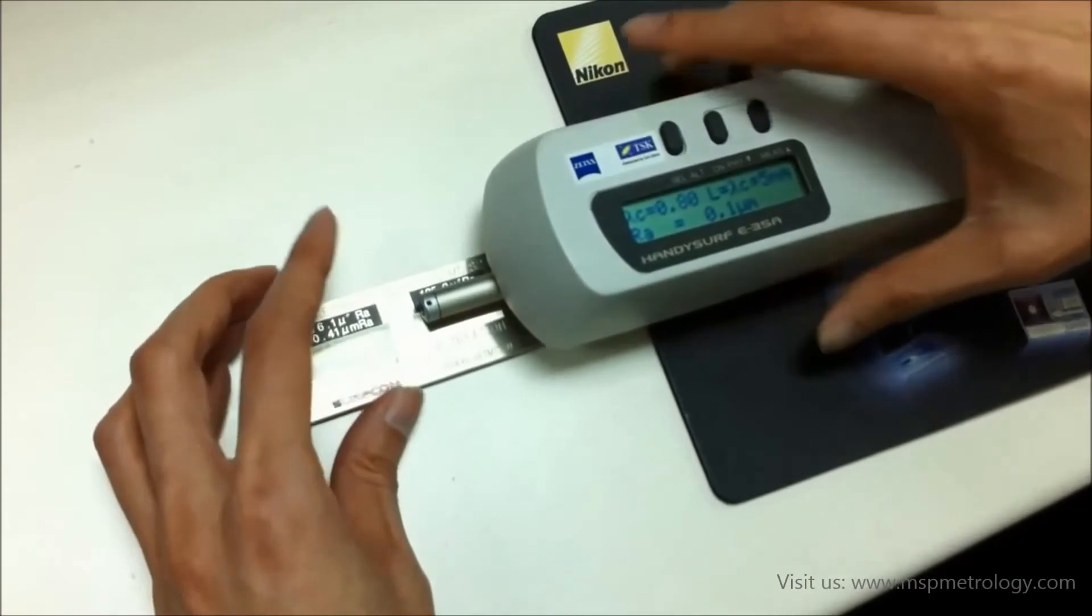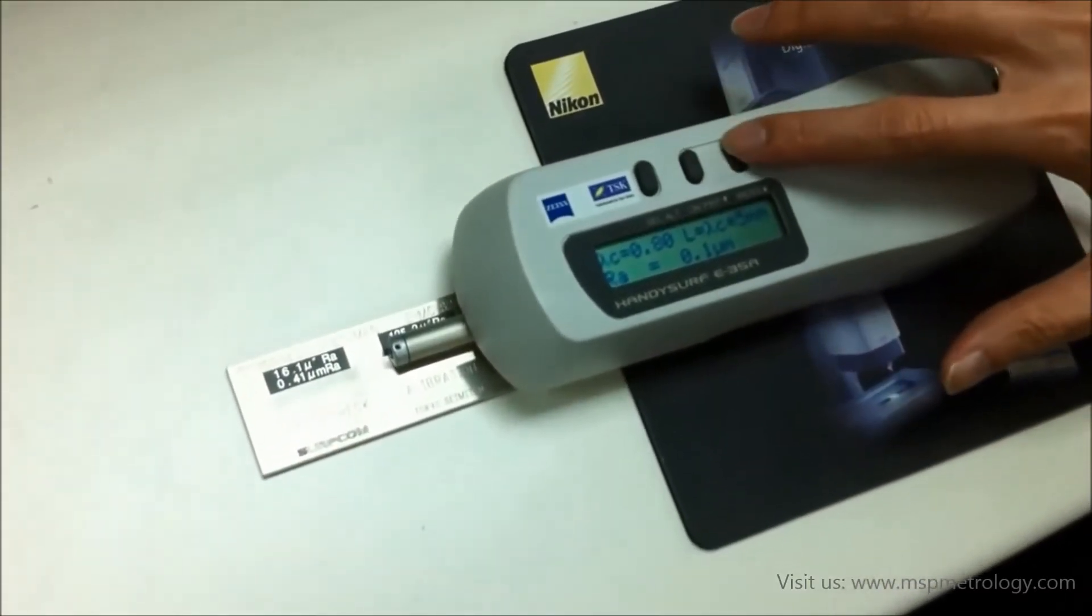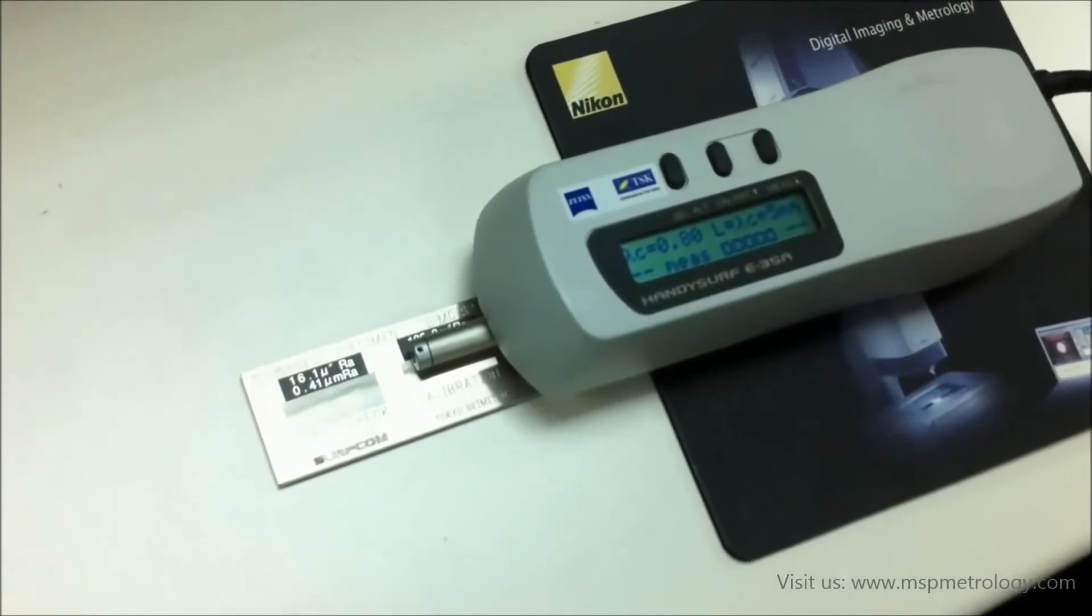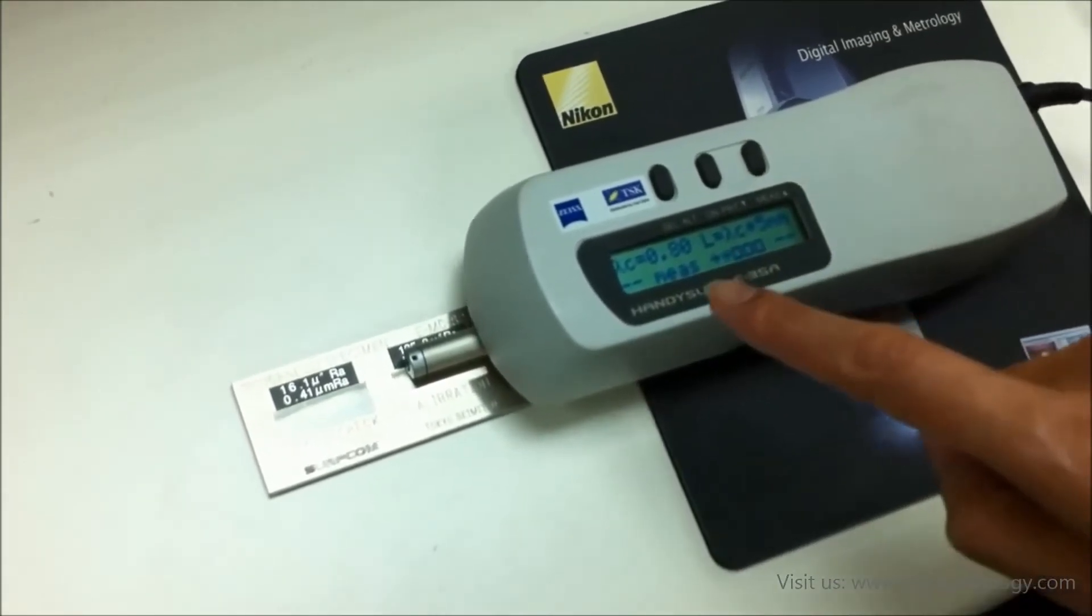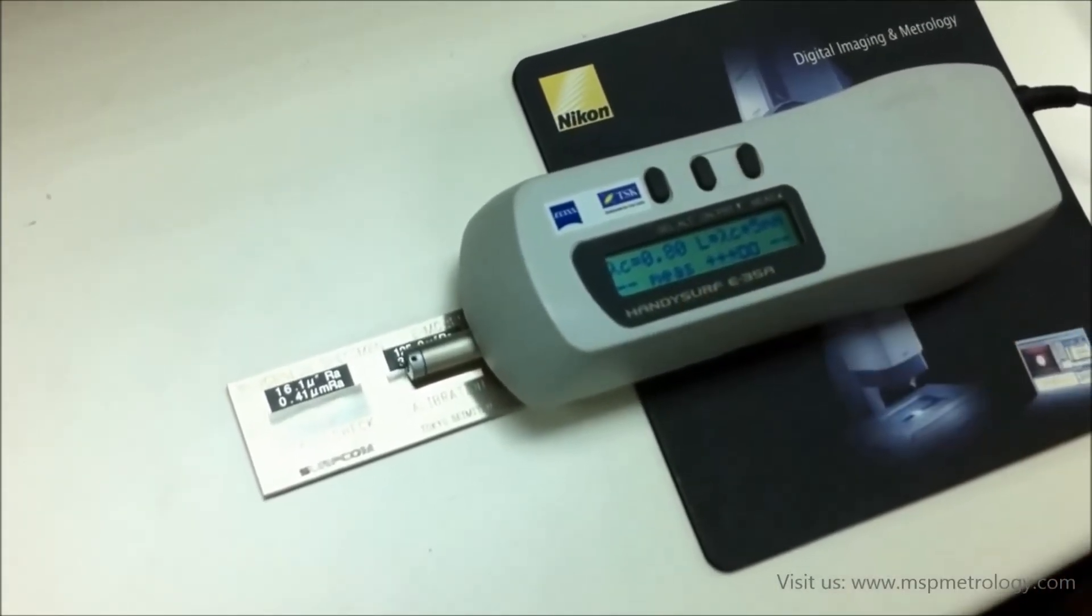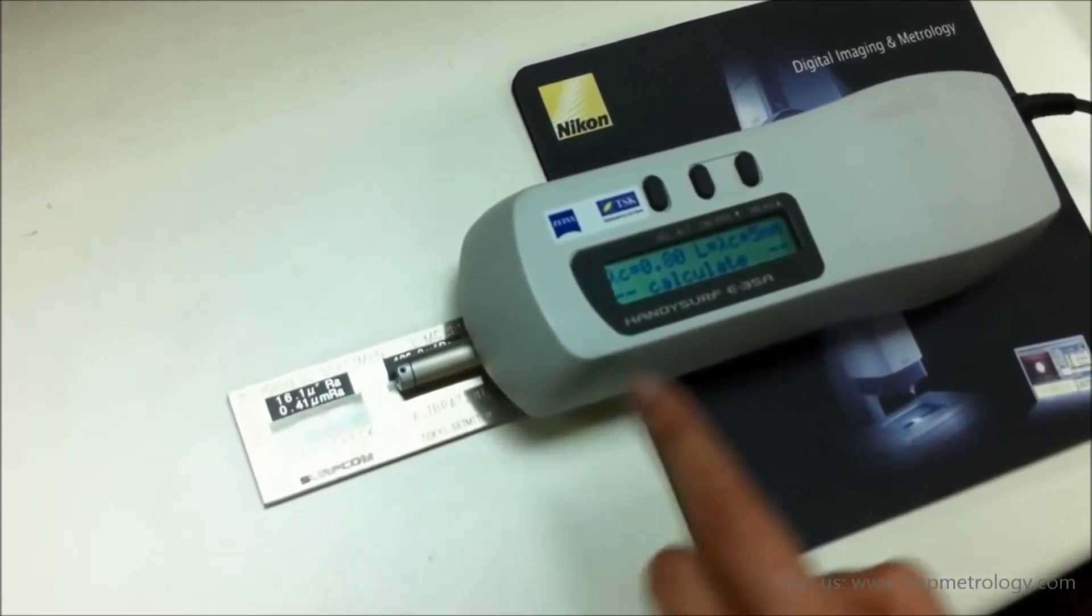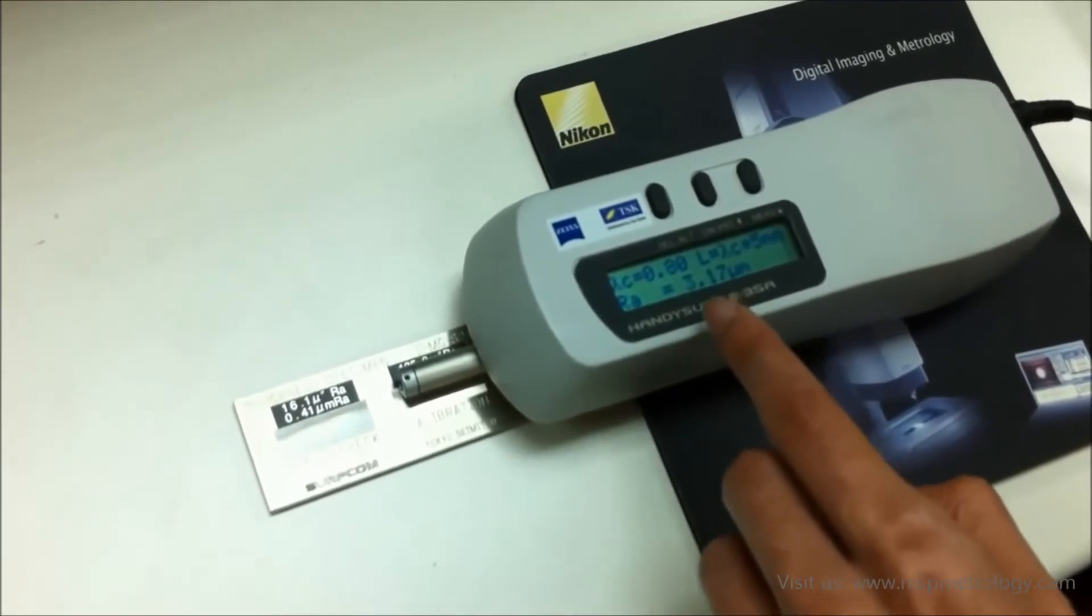Then you press the measure button. You'll see the indicator here showing 'measure' and the status is 'retracting'. After measurement, it does a calculation and shows you the RA value.